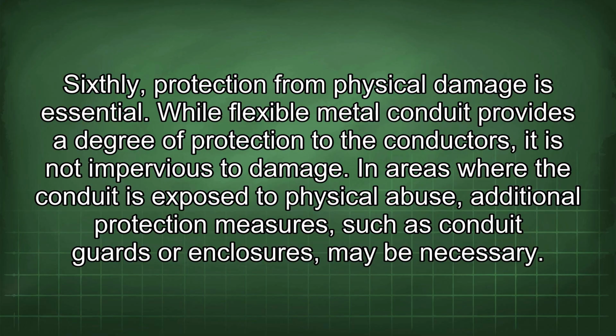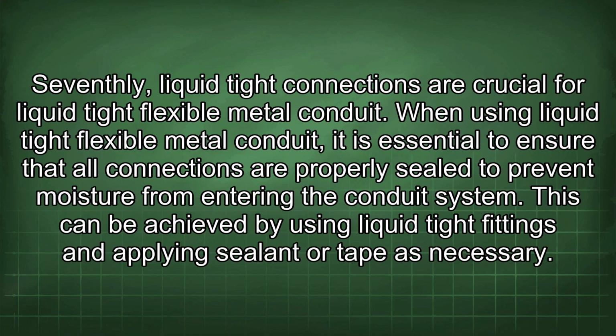While flexible metal conduit provides a degree of protection to the conductors, it is not impervious to damage. In areas where the conduit is exposed to physical abuse, additional protection measures, such as conduit guards or enclosures, may be necessary. Seventhly, liquid-tight connections are crucial for liquid-tight flexible metal conduit.